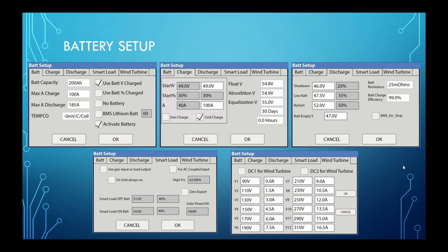Moving on, like David was mentioning earlier, we do have the Smart Load tab. This is where you'll set all the settings for AC coupled, generator input, or if you're wanting to change the generator input into a load output. There are some corresponding settings in there that depend on which one you select. And finally, the wind turbine tab has actually been removed, because we're going to be using that for some later features. The wind turbine tab will not be located on the screen itself, but this will be something similar to what we'll have in the future. So we'll just keep that in mind.